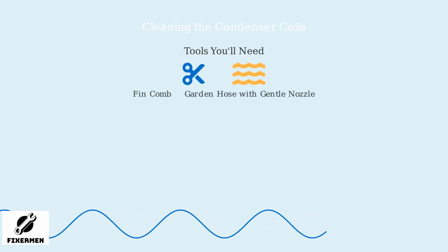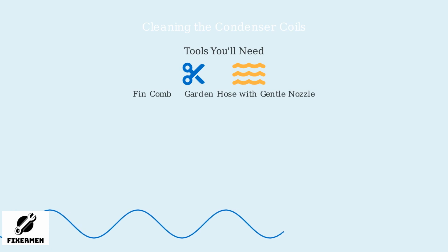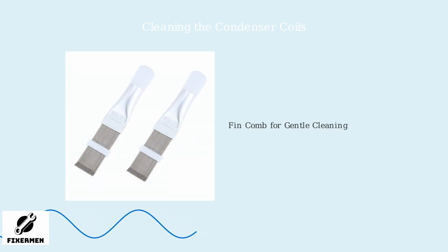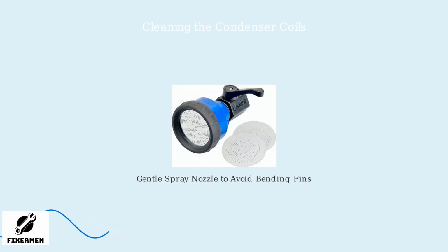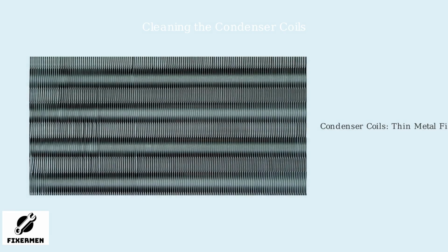To clean the condenser coils, you'll need a fin comb to gently remove debris and a garden hose with a gentle spray nozzle to rinse away dirt. The fin comb has metal tines that help remove dirt without damaging the delicate fins. Use a hose with a gentle spray nozzle to rinse the coils, ensuring the water pressure isn't too high to prevent bending the fins. Before starting, always disconnect power to the unit by turning it off and unplugging it to prevent electrical shocks. The condenser coils consist of thin metal fins that can easily bend. Handle them carefully during cleaning.